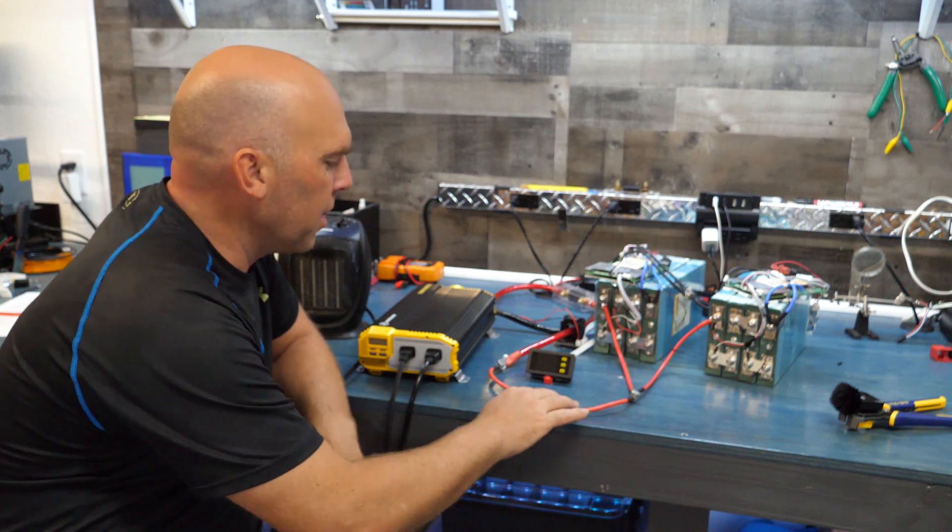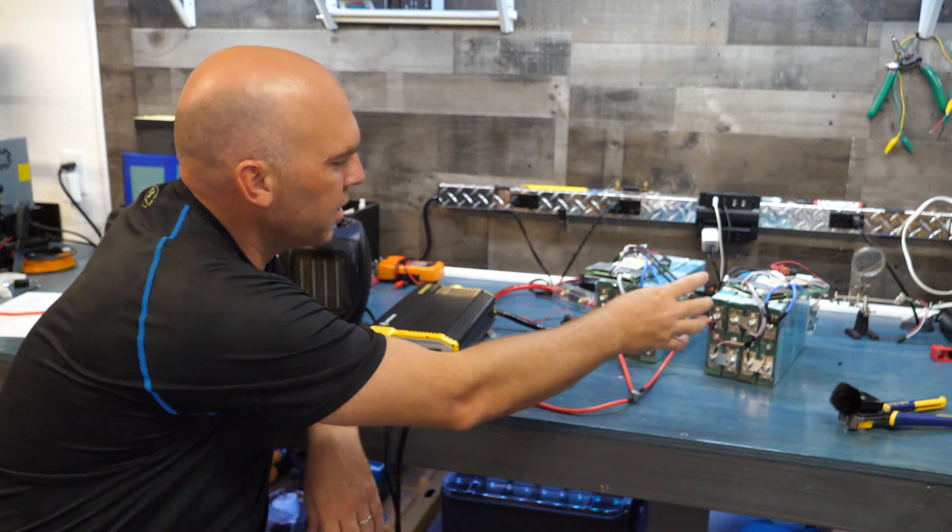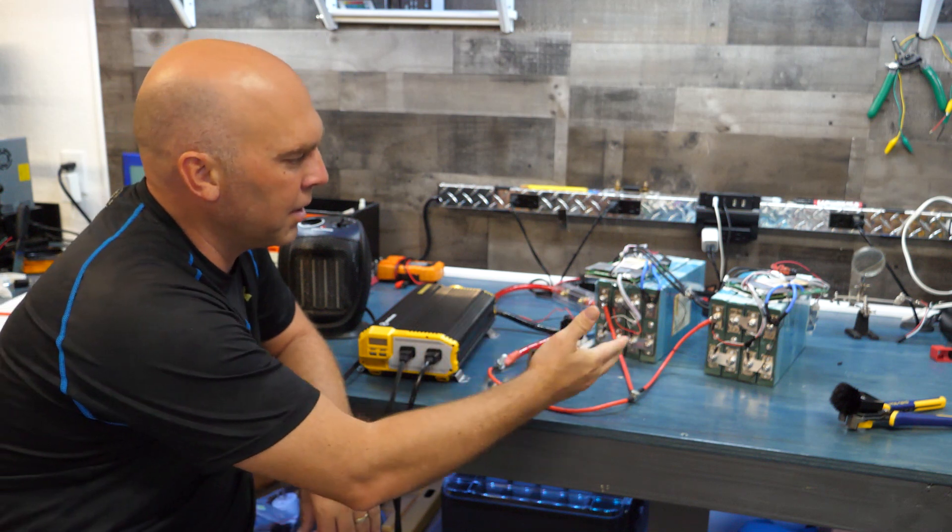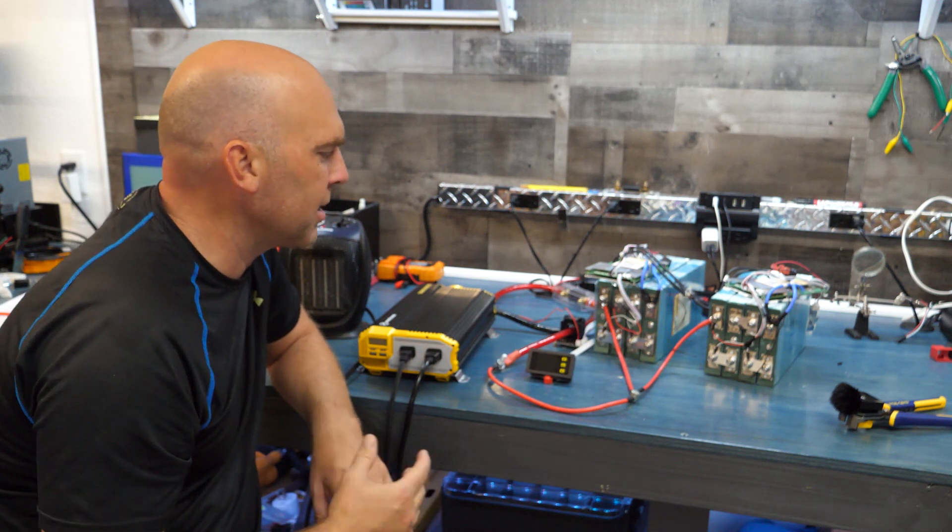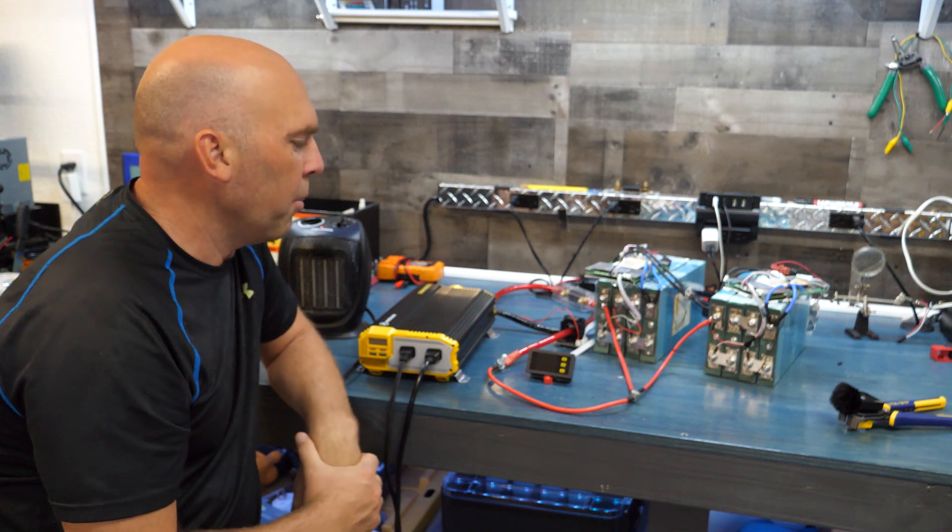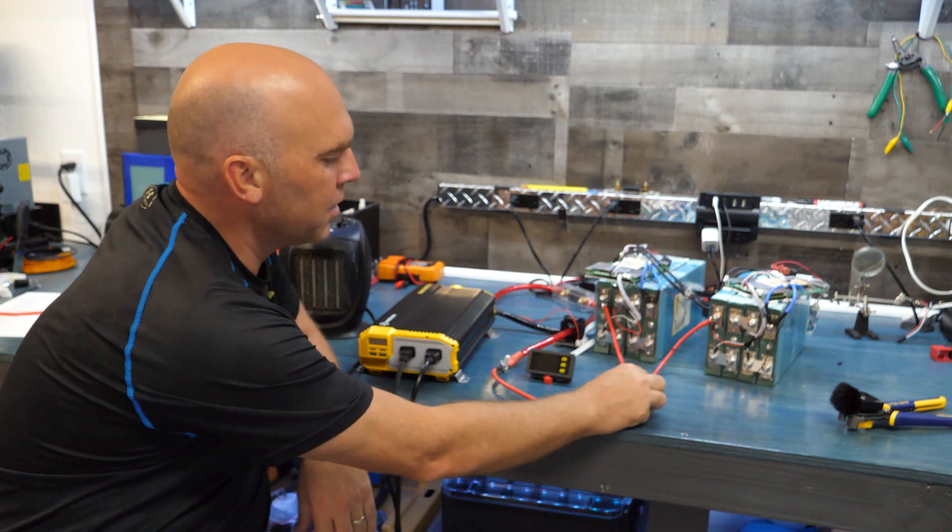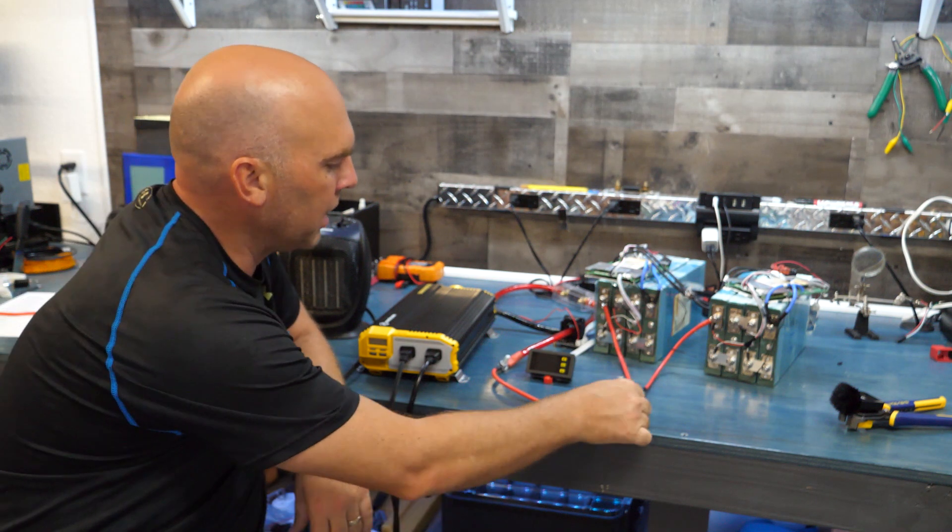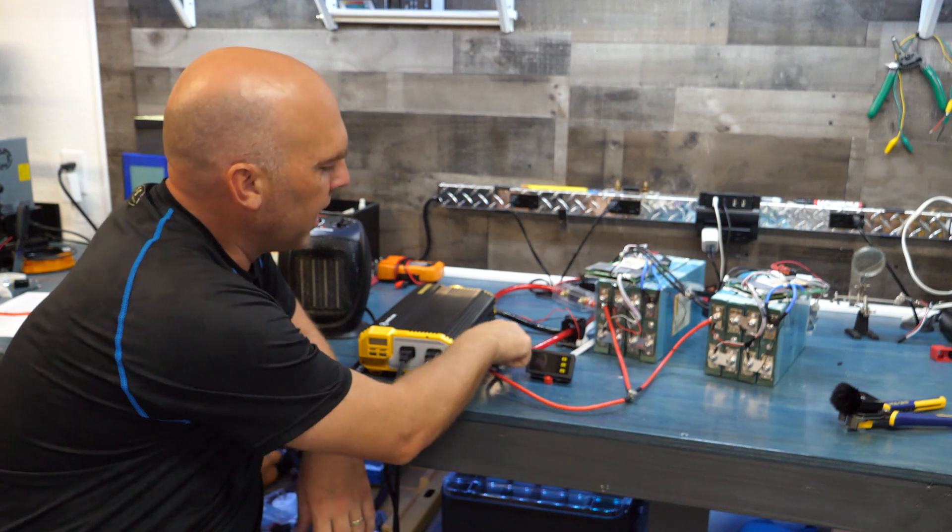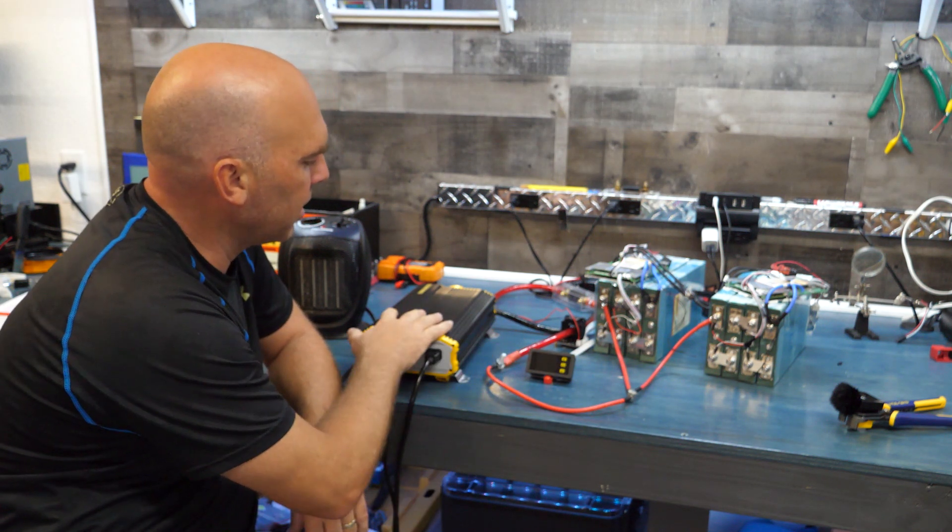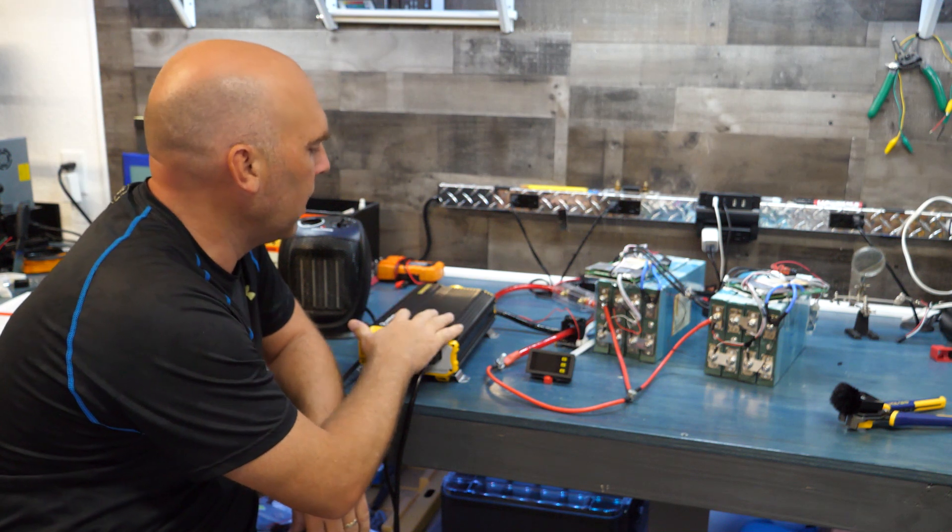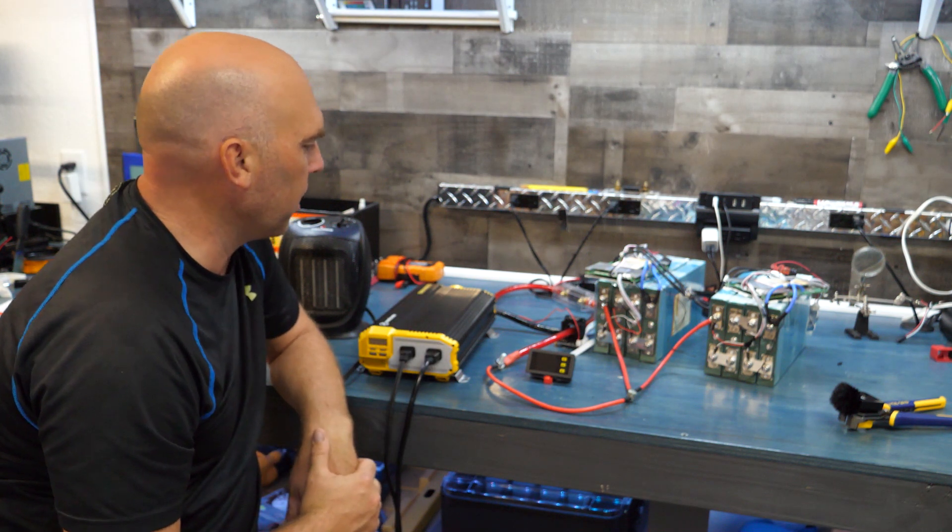This is going to be the bottleneck. So to get to here we have two separate batteries and we have to use two because again if either one of these go over 110 for more than a few seconds the BMS will shut it off. So we put two batteries together in parallel, they join here, we just got them held together with a bolt and then they come down to the one wire for the positive side back into the two awg cable which is connected to two slash zero cable coming over here to the inverter.